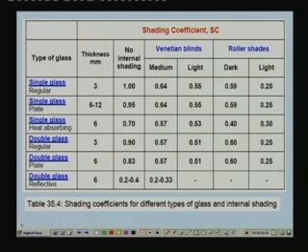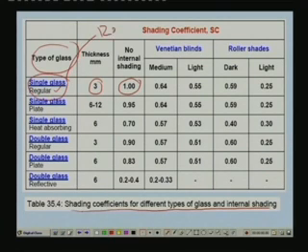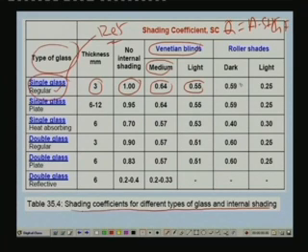An ASHRAE table gives shading coefficients for different glass types and internal shading devices. For a single sheet regular glass of 3 mm (the reference), SC = 1 with no internal shading. With medium Venetian blinds SC = 0.64, light Venetian blinds SC = 0.55, dark roller shade SC = 0.59, and light roller shade SC = 0.25. For regular double glass of 3 mm without internal shading, SC = 0.9. For heat absorbing glass of 6 mm, SC = 0.7.